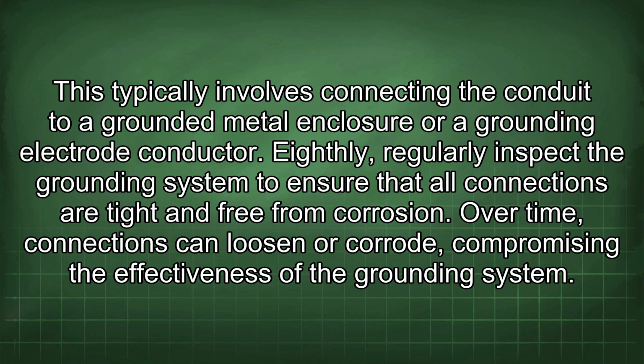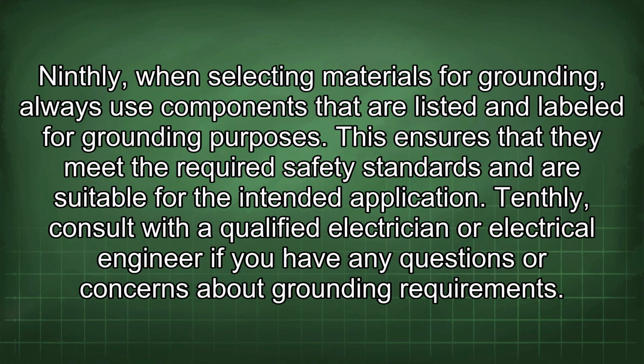Eighthly, regularly inspect the grounding system to ensure that all connections are tight and free from corrosion. Over time, connections can loosen or corrode, compromising the effectiveness of the grounding system. Ninthly, when selecting materials for grounding, always use components that are listed and labeled for grounding purposes. This ensures that they meet the required safety standards and are suitable for the intended application.